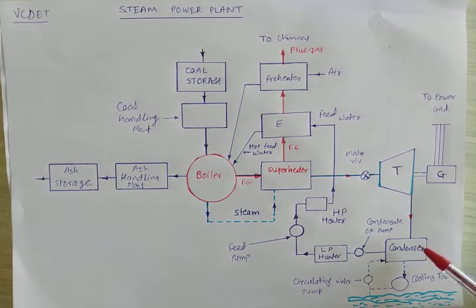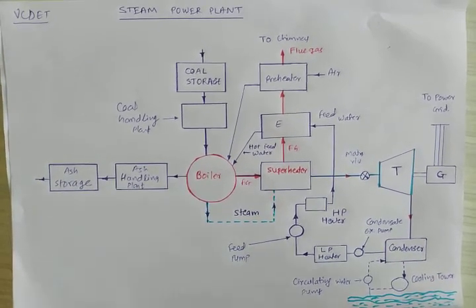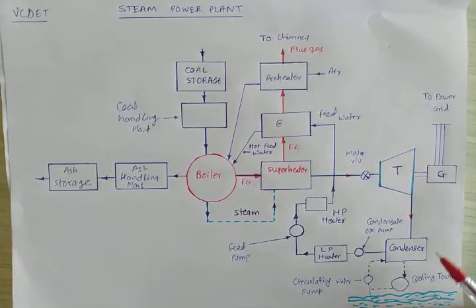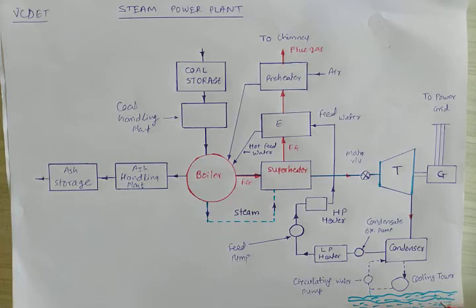A phase change occurs here — from steam to water. When steam leaves the steam turbine and is condensed in the condenser at low pressure, even below atmospheric pressure, a cooling medium such as a cooling tower is used to maintain that pressure. Cold water supplied to the condenser also helps maintain the low pressure in the condenser.